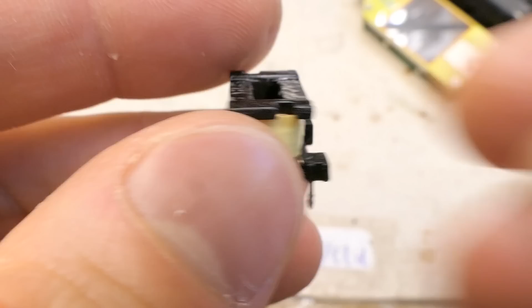Here's the insulation on top. Let's remove it and see the windings: 2 layers of this, then the auxiliary. And of course the auxiliary winding is on the primary side. I don't like how close it is to the secondary ends - there is almost no insulation and insulation distance, especially given how this insulation tape is pre-molten here. It's probably similar.